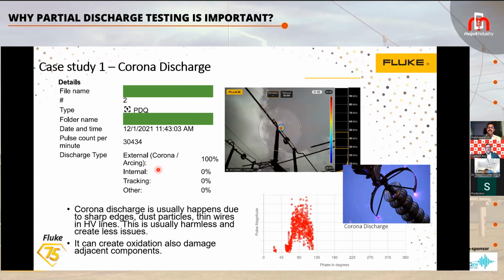And again, each partial discharge has its own frequency range and its own sound. It also gives the indication, like the distance between the camera and the spot, the partial discharge count, and the frequency at which the partial discharge is making the acoustics. And this you can also select, or it can also detect it. That is how it is happening.